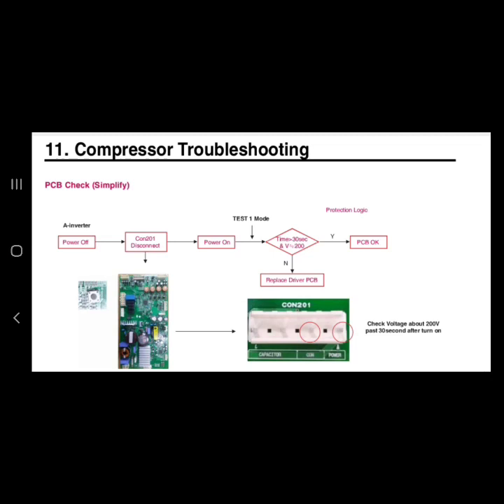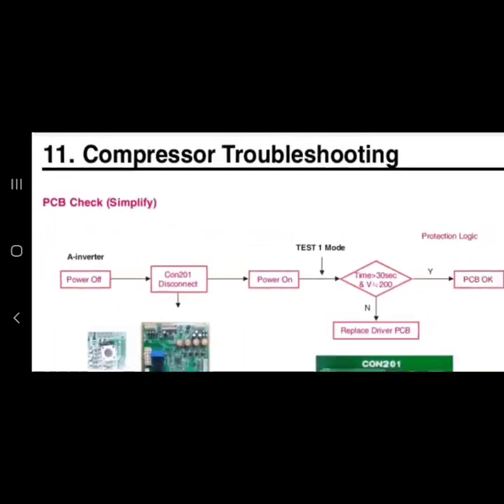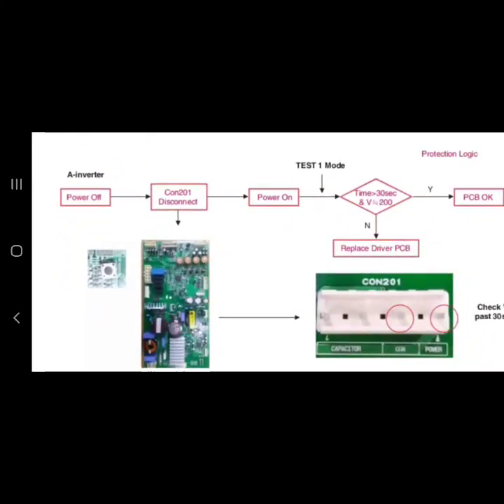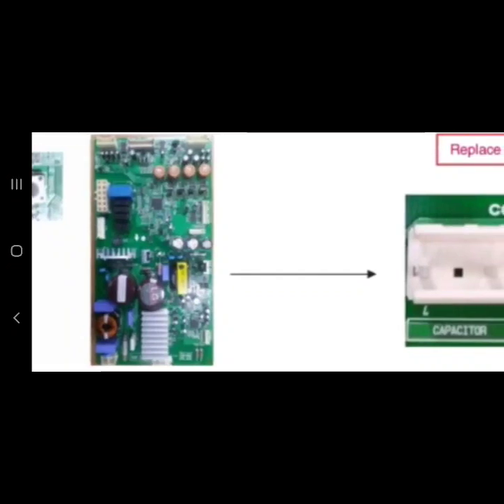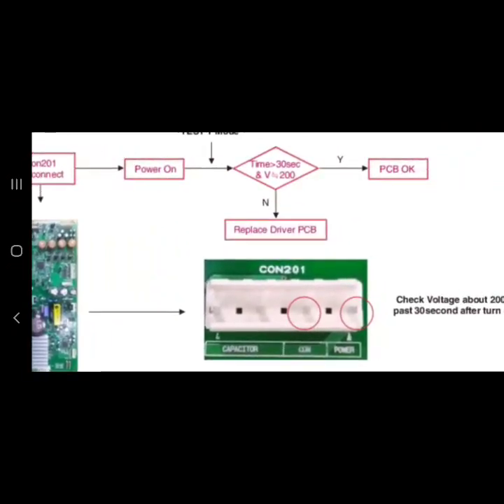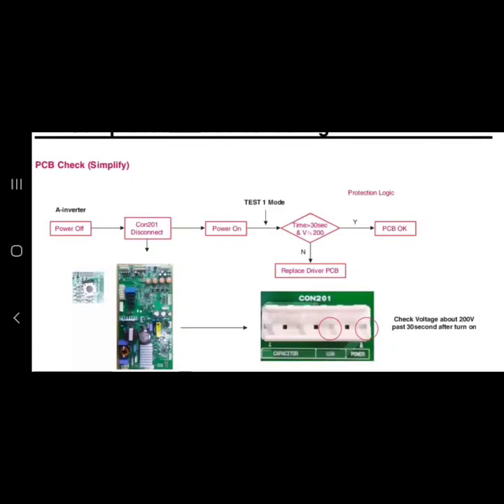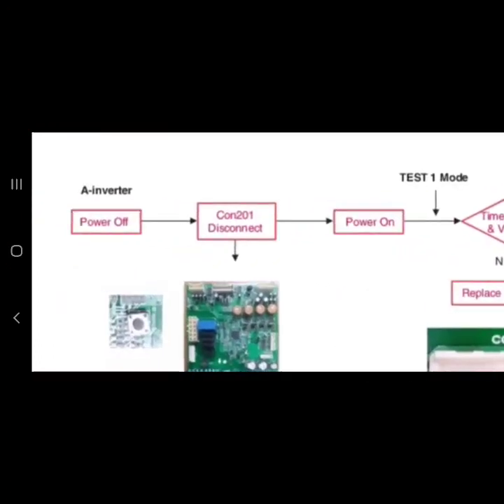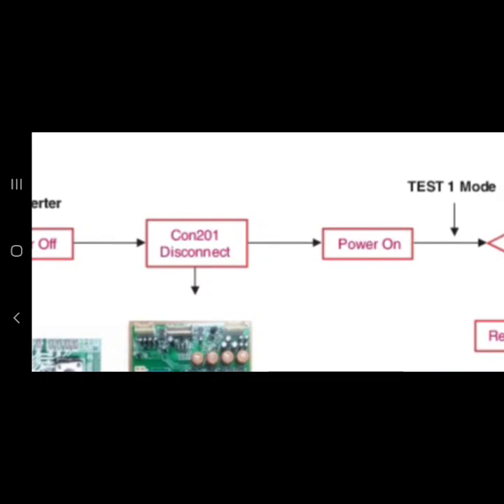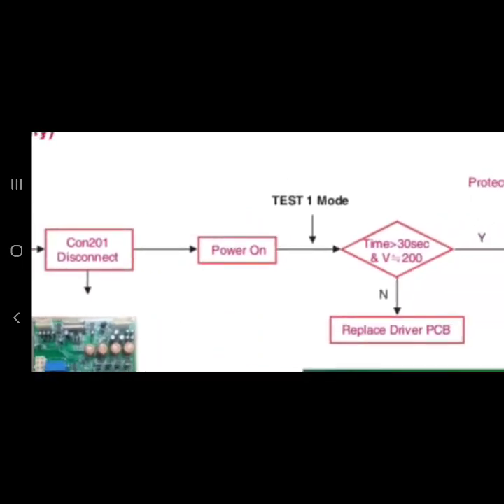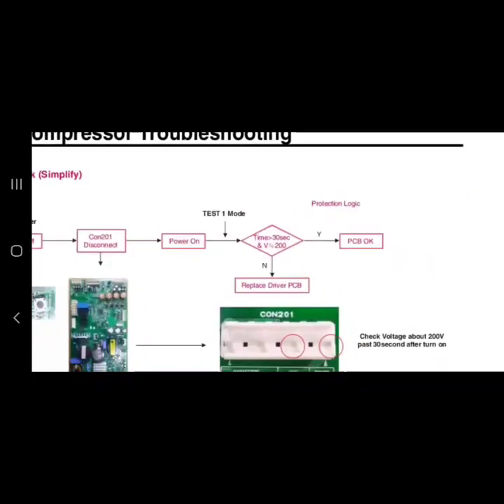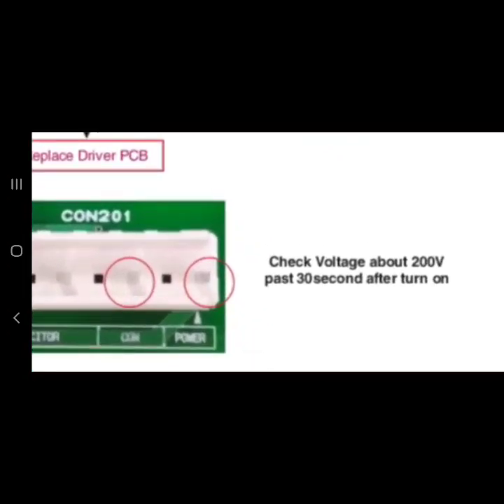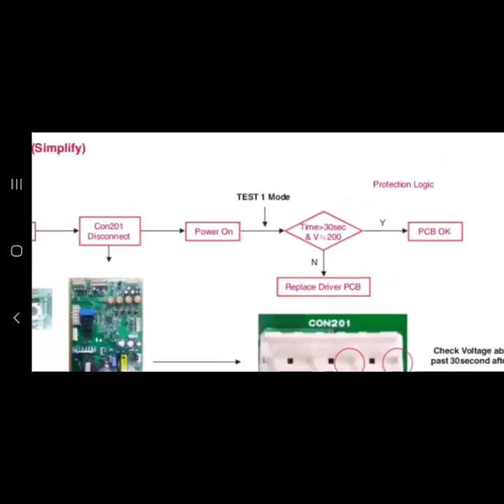So the first thing we want to do is power the unit off. After we power the unit off we want to go to CON201 located here on the board. It's normally right here. CON201, where it says power and comm, that's where we want to put our voltmeter leads and do our measurements. First thing we're going to do is power off, hook up our leads to CON201, then power it on. Now once we power it on, if you notice here they want us to check voltage about 200 volts AC past 30 seconds after turn on.